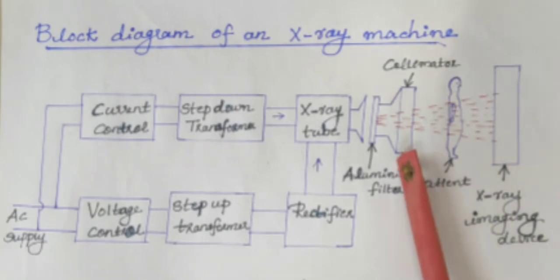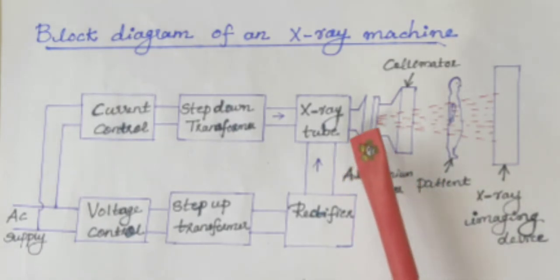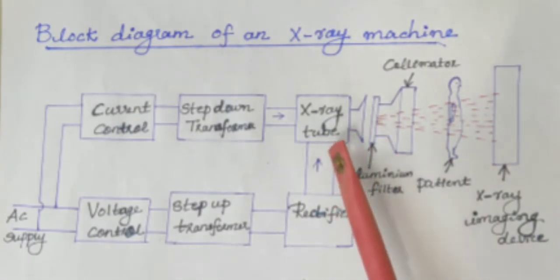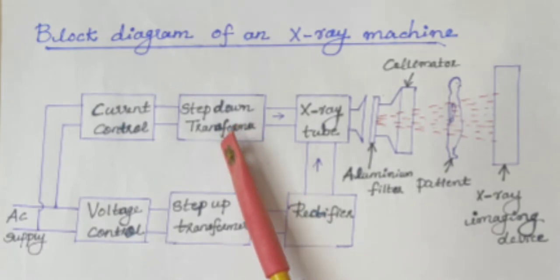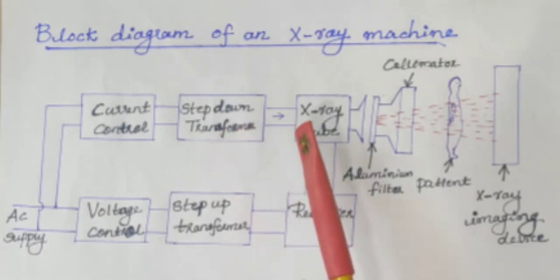Cathode is supplied with a low AC voltage and anode with a high DC voltage. In order to supply low AC voltage to the cathode, AC supply is stepped down using a step-down transformer and given to the cathode.